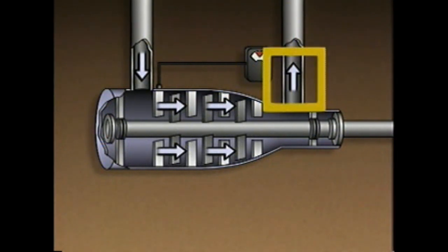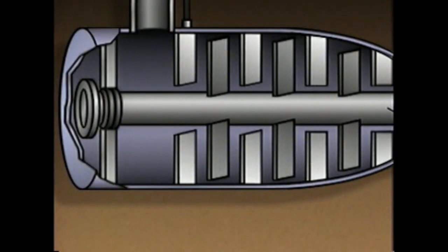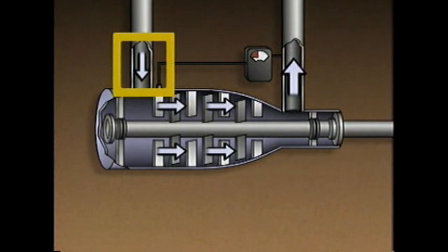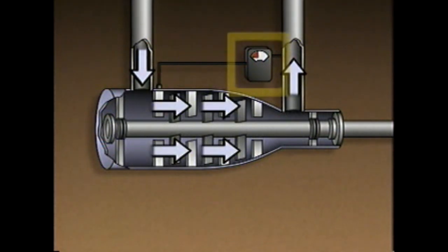As long as gas flow through a compressor matches the demand for gas, the discharge pressure also remains constant. When the demand for gas increases, discharge pressure begins to drop. The pressure controller responds to the change in pressure by opening the inlet guide vanes, which allows more gas to enter the compressor. When more gas enters the compressor, more gas can be compressed, and as more gas is compressed, the discharge pressure increases until it returns to its desired value.